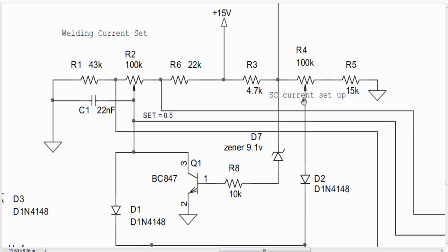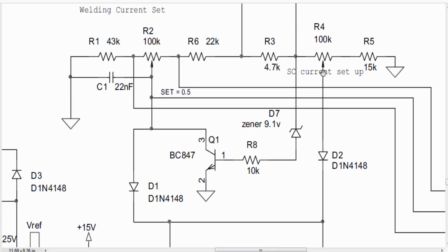Then there is the short circuit detection setup. If we connect this at 200 ampere, we have to set it slightly above 200 ampere, so that above 200 ampere it indicates there is a short circuit. This is the setting. If it does not have a short circuit detection circuit, we just have this potentiometer, and in that case we have this sampling circuit.